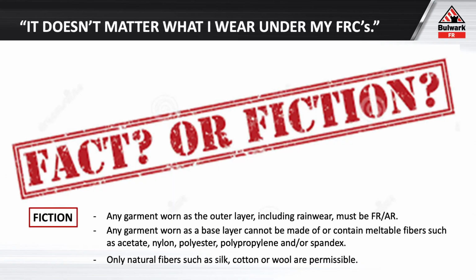And the reality is, obviously, that's fiction. Any garment, first and foremost, in a short-duration thermal hazard has to be flame resistant and/or arc rated. That includes your rainwear, your vests, your winter jackets, your hoodies—anything that's going to be the outermost layer has to be able to protect you in the hazard you're looking to experience.